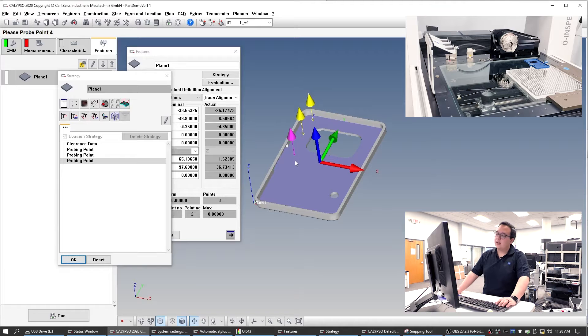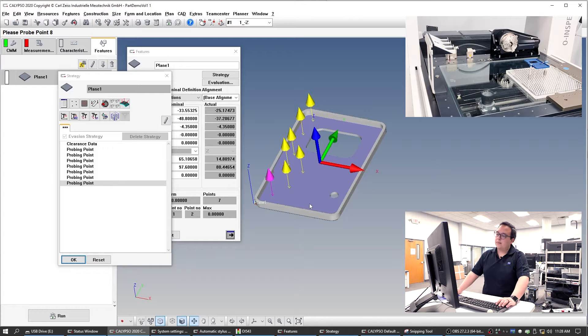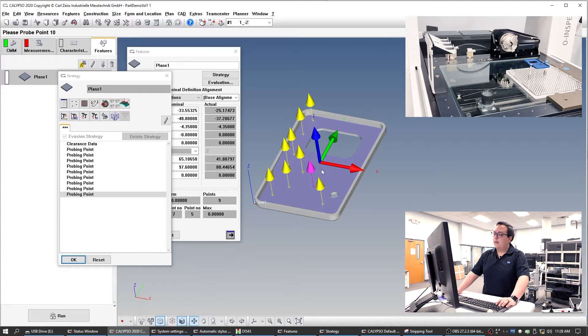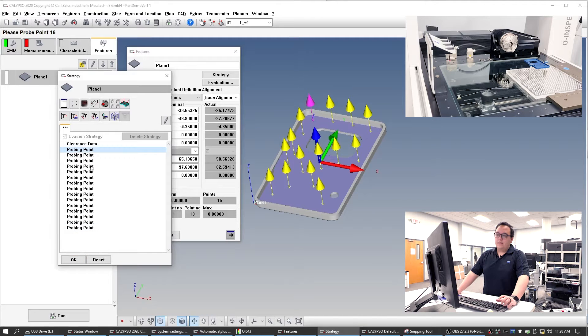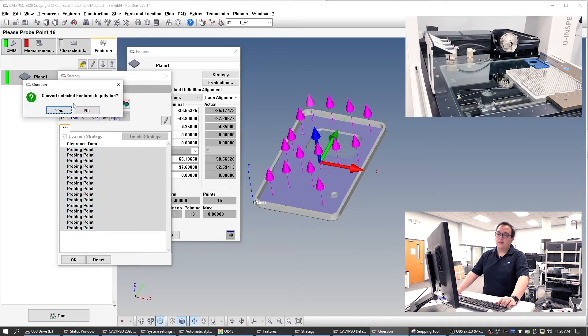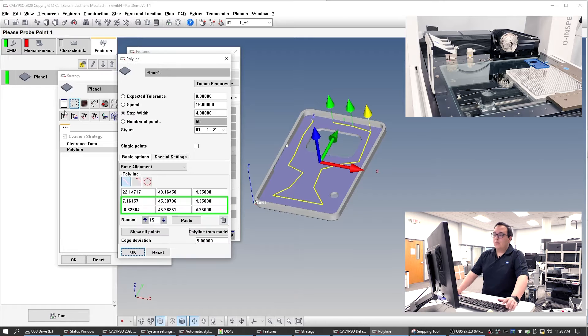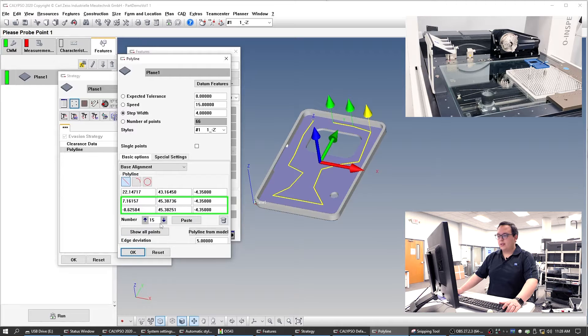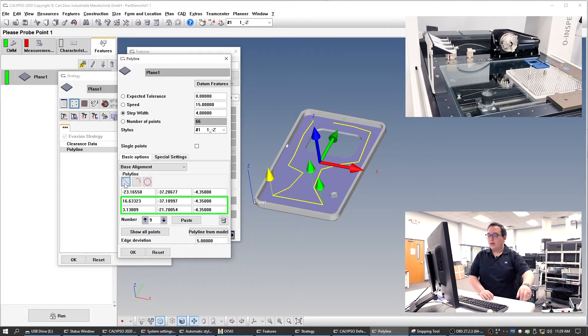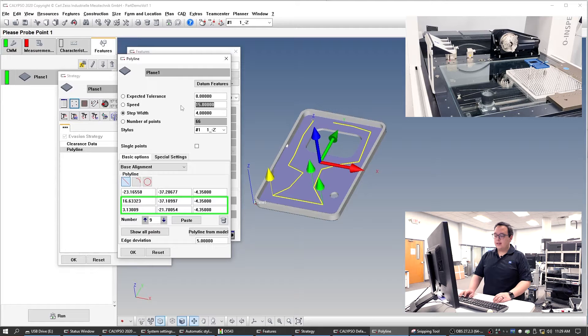We'll just go around here, avoiding that, and highlight all these points. Let's go ahead and make this into a polyline. We see a couple of the points here — it's very squared off, so I'm going to go to where we see those really sharp corners and see if we can't make them into circles. We're going to have to take them as straight lines — not to worry, the actual CMM will curve the edges some amount. 15 for a speed on a passive sensor is actually really high. If we still want to go really fast, I think the max I would do is 10, but let's go for 7.5. We don't want this to be a slow program initially, but we do need it to be reasonable.